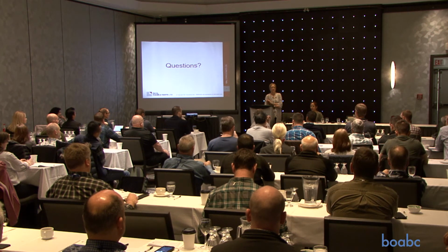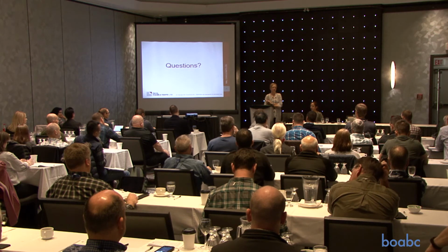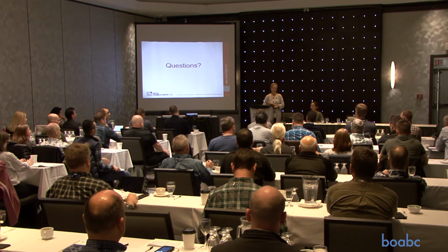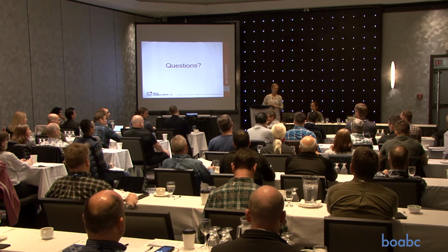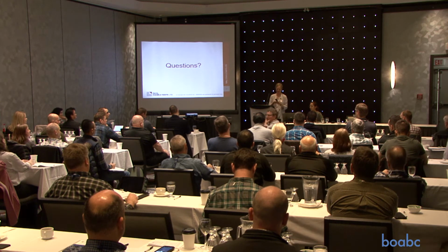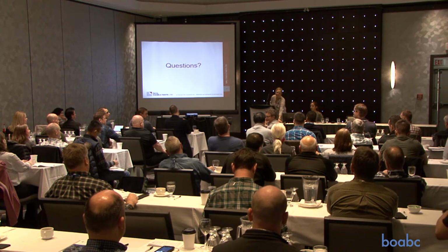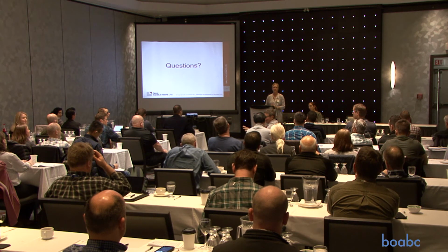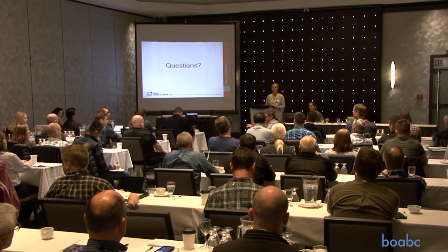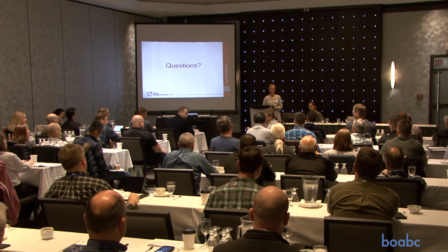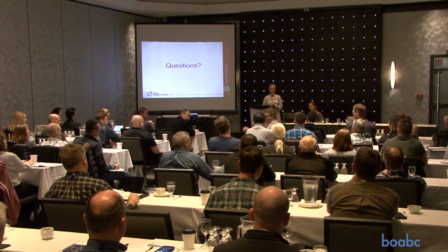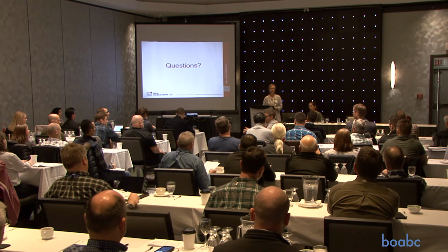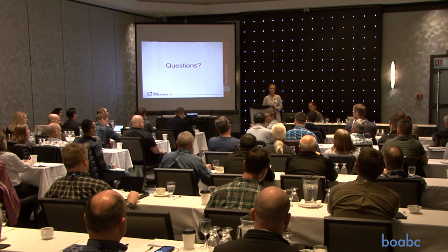Can anybody hear what Dave's saying there? No. So, do you want a mic? I've seen a lot of rated T-bar ceilings in old plans, in old buildings, and I do fire inspections, and they're not up to work. They do work when they were put in, but they sure don't work 30 years later when they've been modified 17 times.